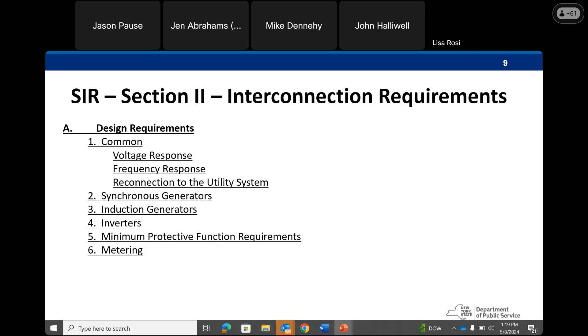It continues in terms of interconnection requirements, covering operating requirements, requirements for dedicated transformers, disconnect switch, power quality, power factor, and islanding. Equipment certification is a big one too. We require all inverters to be certified and tested to UL 1741, the latest version, which is the guidance for IEEE 1547. The latest version now is the SB version, and that's all identified in there.